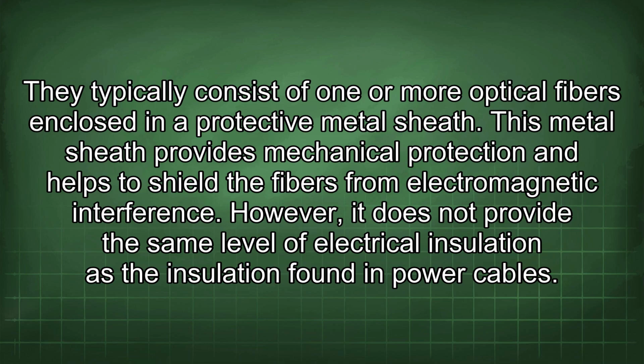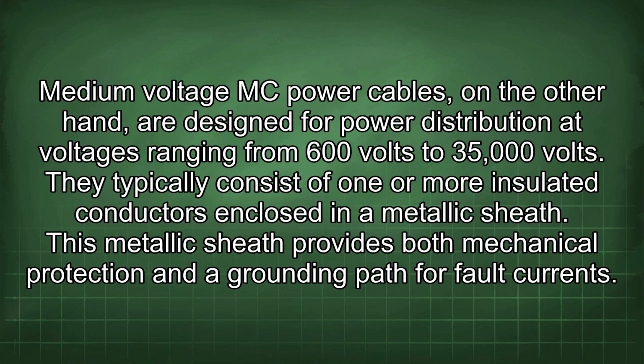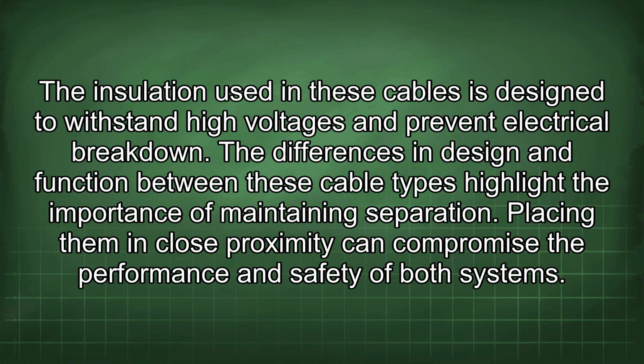However, it does not provide the same level of electrical insulation as the insulation found in power cables. Medium voltage MC power cables, on the other hand, are designed for power distribution at voltages ranging from 600 volts to 35,000 volts. They typically consist of one or more insulated conductors enclosed in a metallic sheath. This metallic sheath provides both mechanical protection and a grounding path for fault currents. The insulation used in these cables is designed to withstand high voltages and prevent electrical breakdown.